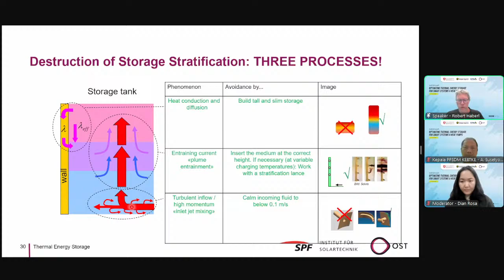Here you see a CFD simulation of a storage tank that has in the beginning a good stratification, 50 degrees at top and 30 degrees in the lower part. And you have an inlet in the middle of the storage tank. And you see here what the way of the fluid is. It goes fast all the way through the tank to the other side of the storage volume. And there it is distributed all over the storage tank, and then you reduce your temperature profile in a short period of time and mix the hot water down to a lower temperature.